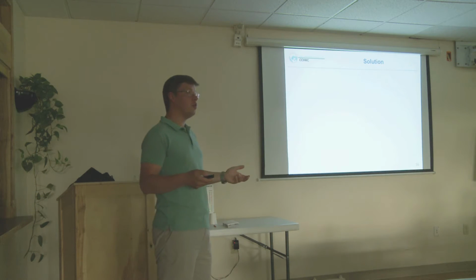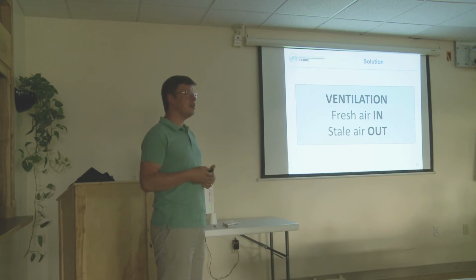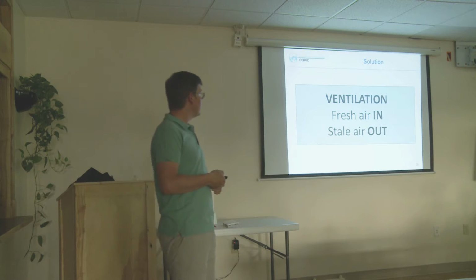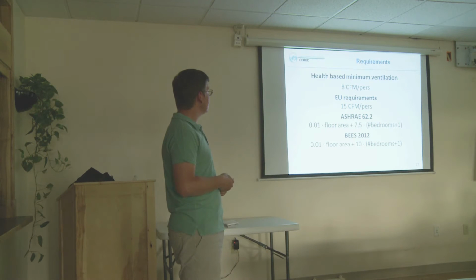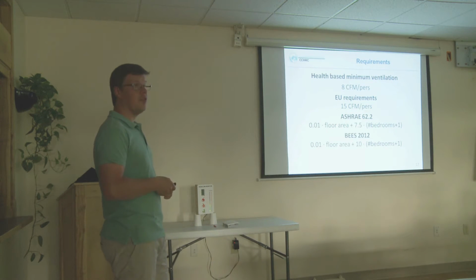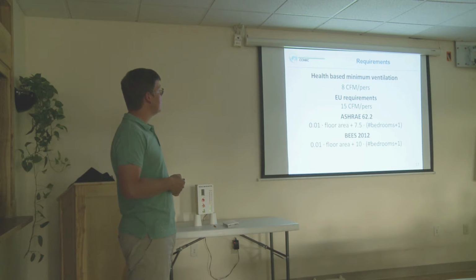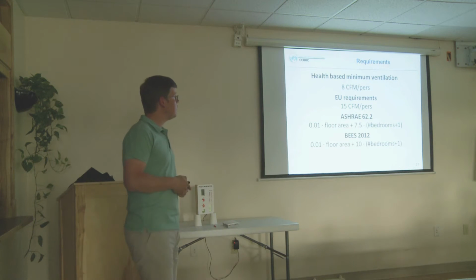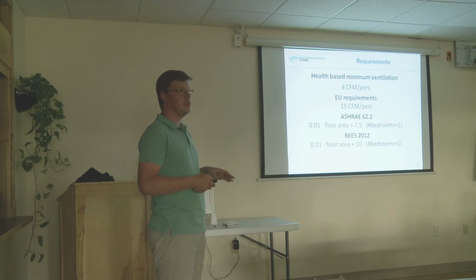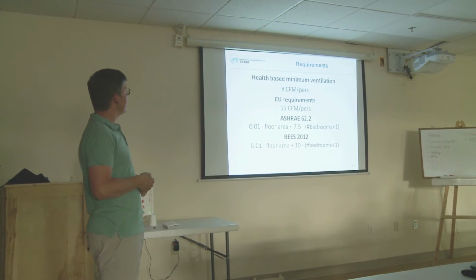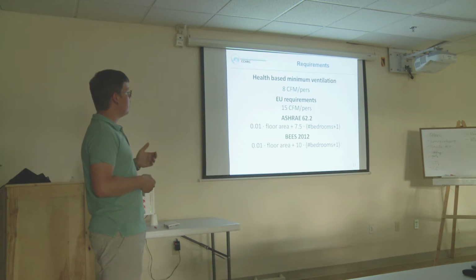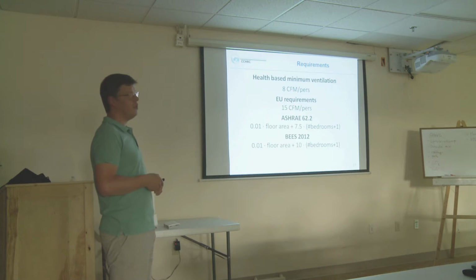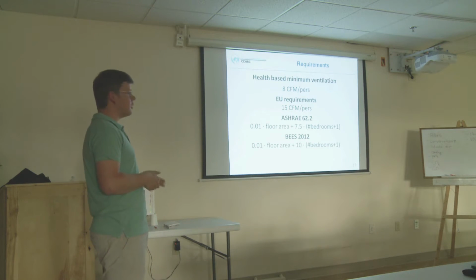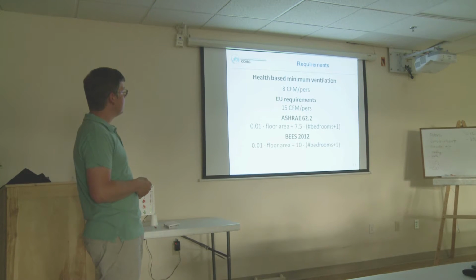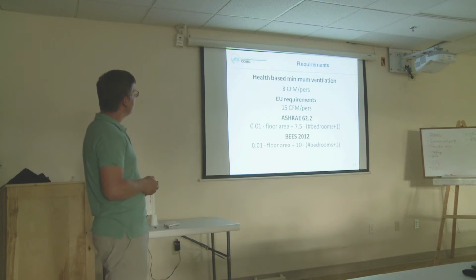So what is the solution to poor indoor air quality? We need to get some fresh air in and get that polluted and stale air outside. And how do we do that? We're going to get to that in a minute. There are some requirements for ventilation. There is a health-based minimum that is 8 cubic feet per minute per person. That is the absolute minimum a person needs to thrive. However, there are European and American requirements, which both basically say the same thing, just in a different way, that there should be about 15 cubic feet per minute for every person. Then there is the Alaskan requirement, which is a little more strict than the American one, and we will see that best in the example right here.